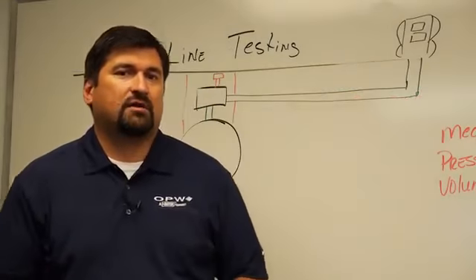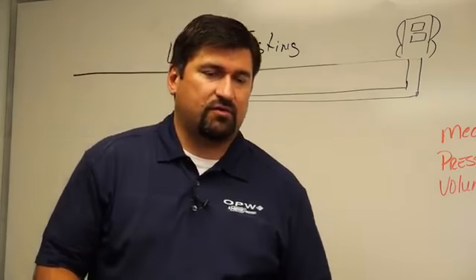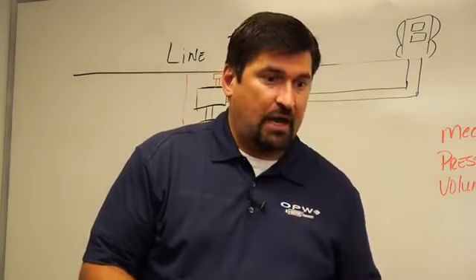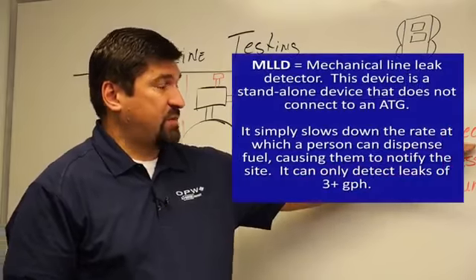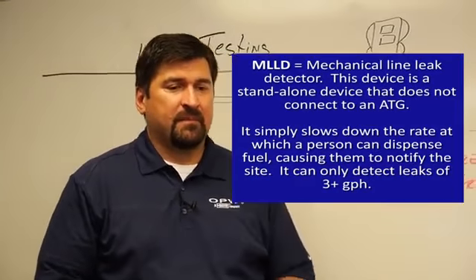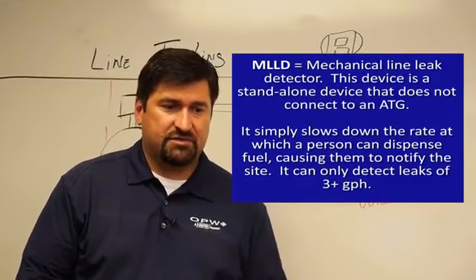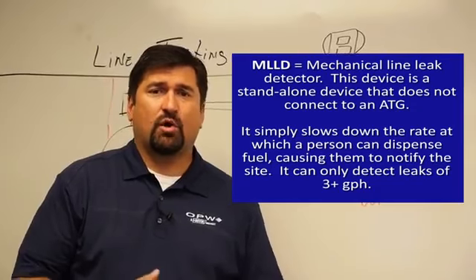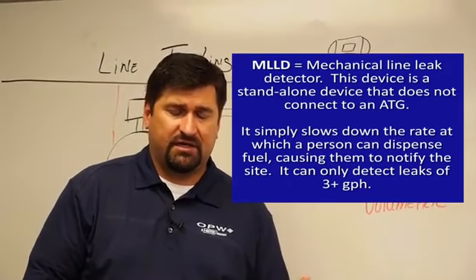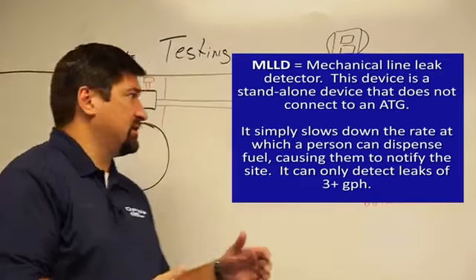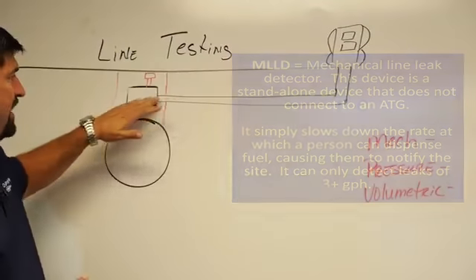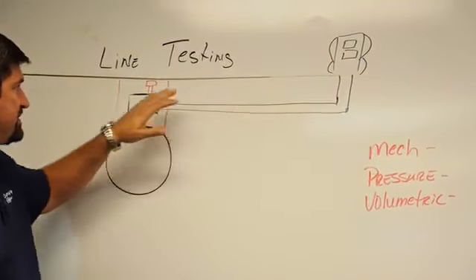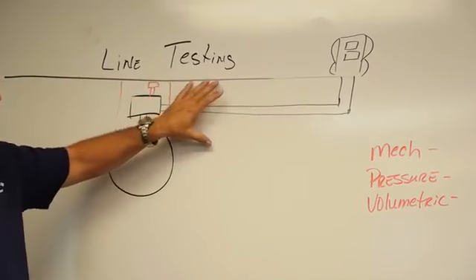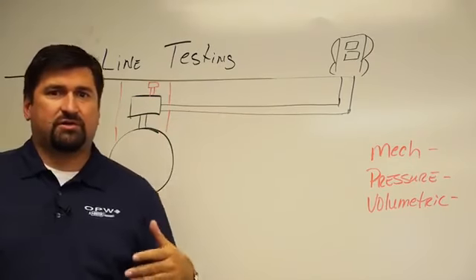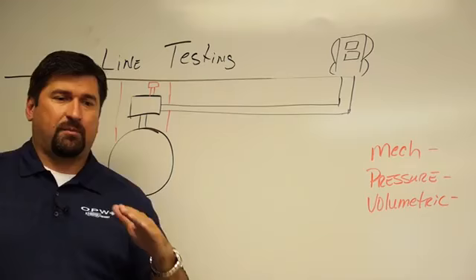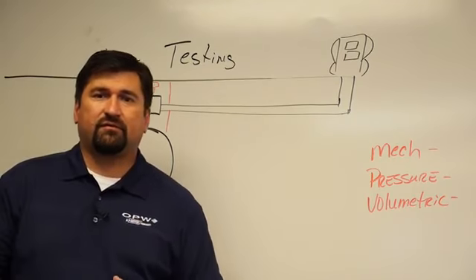Earlier in the video, we talked about line testing as part of your regulatory requirements. One of the most common and most widely used is probably the mechanical line leak detector. Now, a mechanical line leak detector is just that. It's a mechanical device. There's no electronics in it. It doesn't talk to an ATG. But basically what it's doing is monitoring the pressure of the underground piping to the dispenser from the motor. And at the point at which it reaches a certain pressure, depending on the manufacturer, the poppet will actually close, restricting flow.